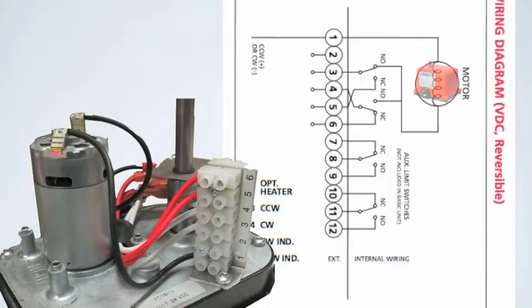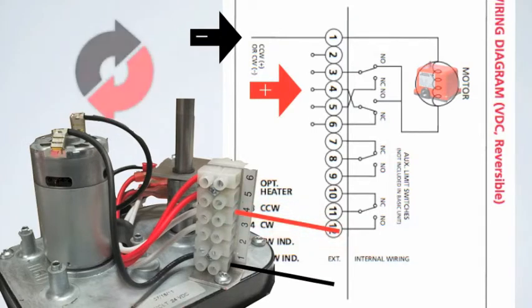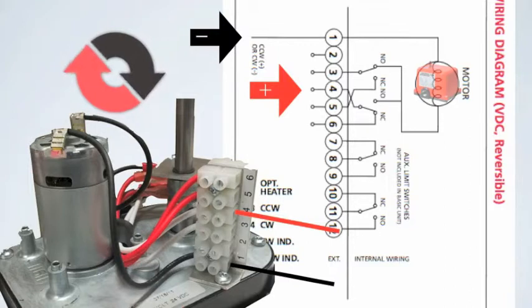To close or drive the actuator in the clockwise direction, apply negative DC voltage on terminal 1 and positive on terminal 4. The actuator will turn clockwise until it reaches the internal limit switch and shuts off.